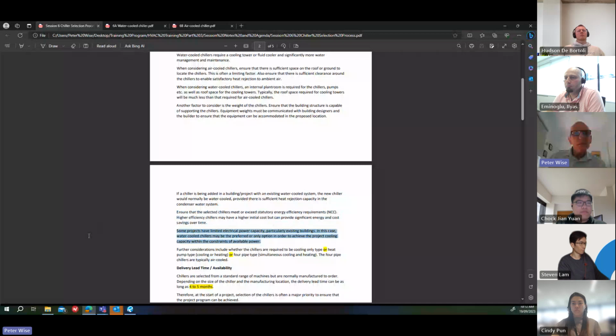Some projects, and existing projects, have limited electrical power capacity. You might come across this situation. In this case, water-cooled chillers may be the preferred or only option in order to achieve the project cooling capacity within the constraints of available power. Now, that probably sounds like a bit of a silly thing to say, but it does happen. It mightn't happen very often, but you might find during your working life that this comes up.